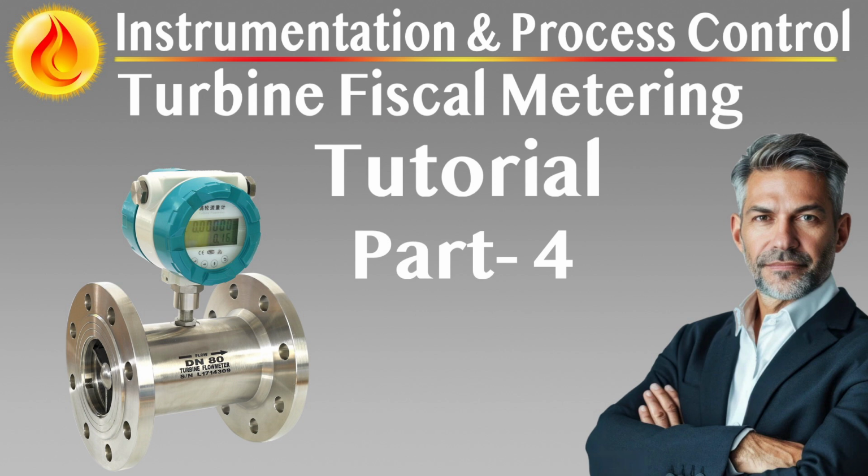Heat soak and stability testing. The complete metering system, including control electronics, must undergo extended heat soak testing at elevated temperatures, typically 45 degrees Celsius, for at least 100 hours.